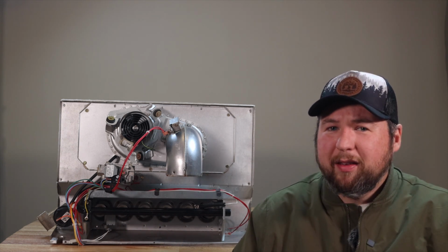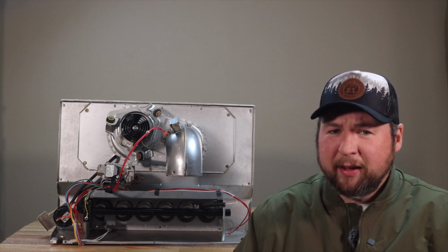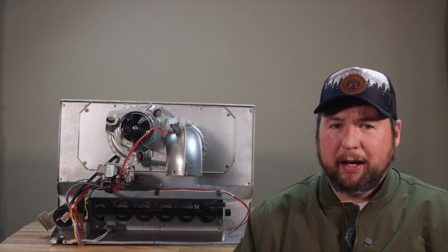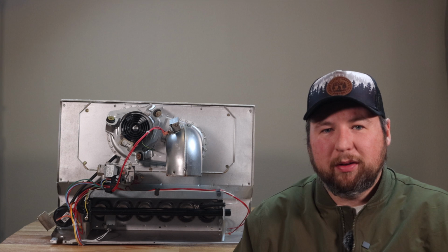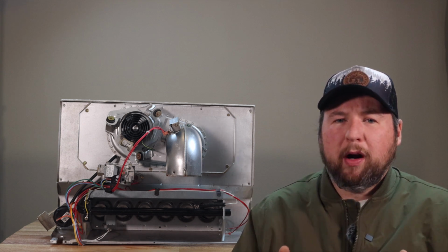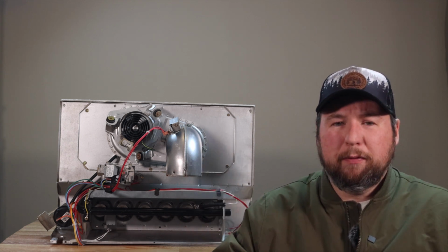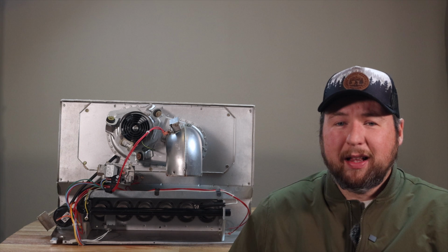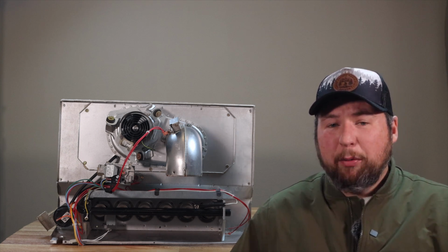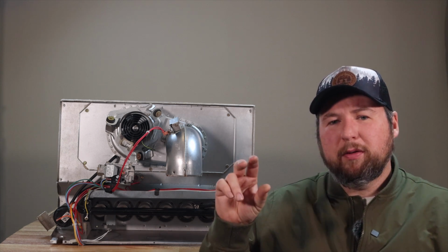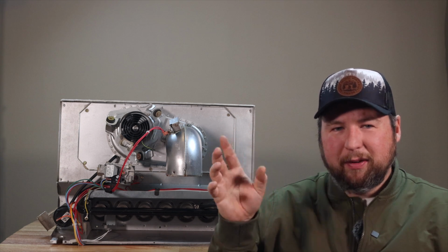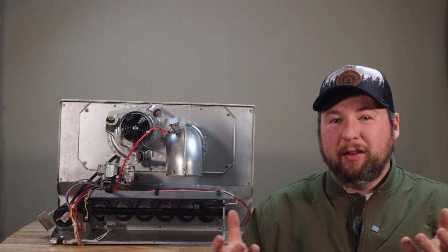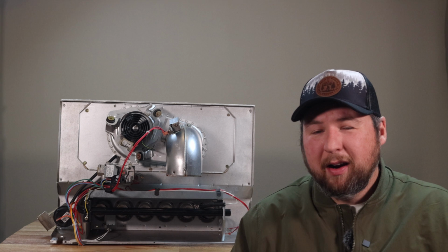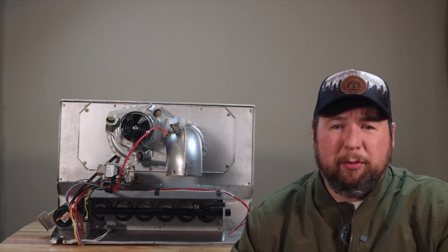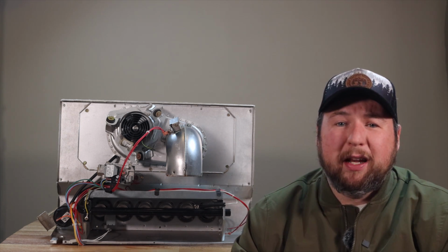But because of the style of them, it's literally just got a ribbon burner in a metal box, so it's just not very efficient. There were some where they would go hybrid. They basically throw an inducer on a clamshell heat exchanger, and that would help a little bit. And then they would also put divots and different stuff to expand the surface area to transfer a little bit better. But that's when they basically were like, we need to redesign it, and they came out with the 80%er.